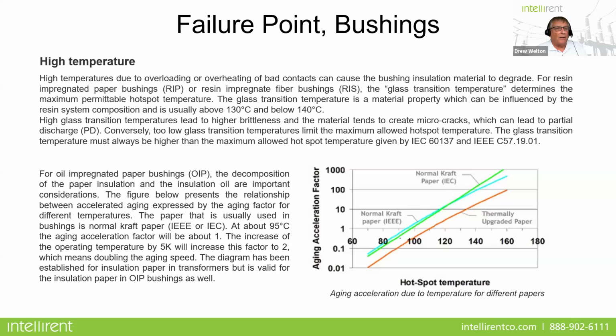High temperature is another thing. High temperatures due to overloading or overheating of bad contacts can cause bushing insulation material to degrade a lot faster than it should. For RIP, your resin impregnated paper bushings, or resin impregnated fiber bushings, the glass transition temperature determines the maximum permissible hotspot temperature. So the glass transition temperature is a material property which can be influenced by the resin system composition. And this is usually above 130 C and below 140 C respectively.